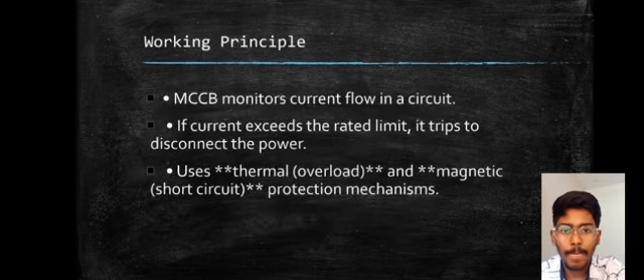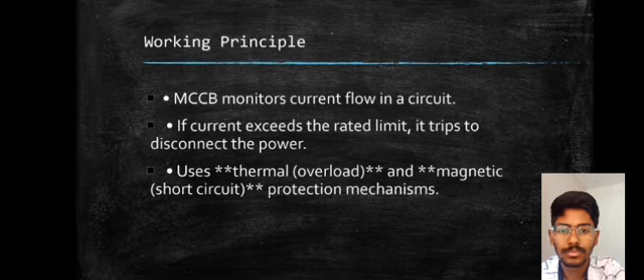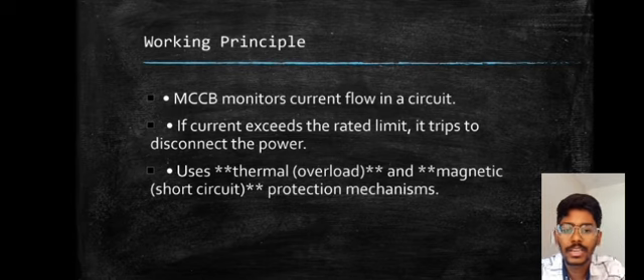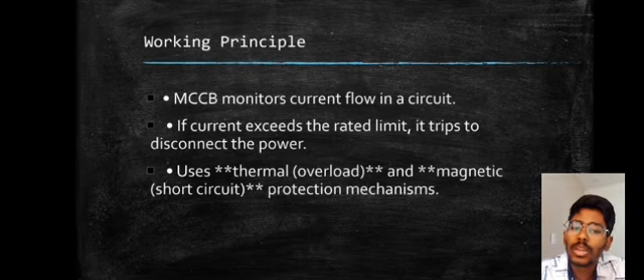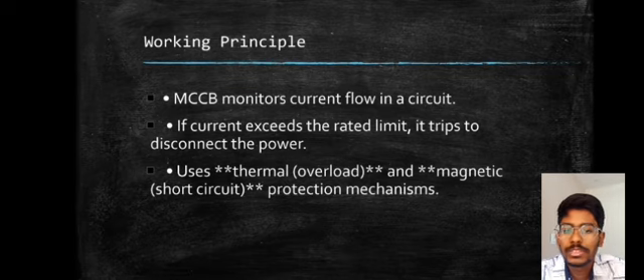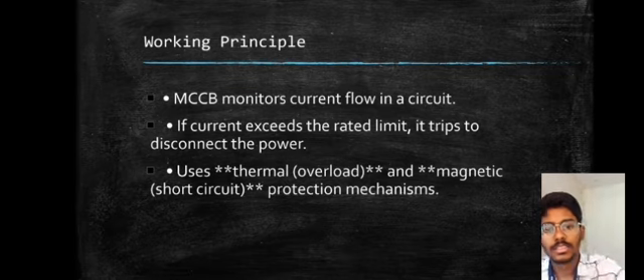MCCBs work by using a thermal magnetic trip mechanism. Thermal trip protects against overloads when excess current flows for a prolonged period, and a bimetallic strip bends and trips the circuit. Magnetic trip protects against short circuits. Sudden high currents activate a solenoid which trips the breaker instantly.